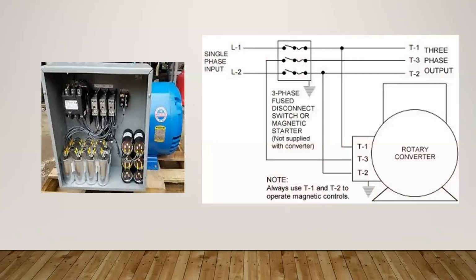The other one that's very heavily in the market is what they call rotary phase converters. And literally what that is, is an induction motor with the shaft cut off. When a motor gets up to speed, it creates a rotary transformer, meaning that it puts counter EMF voltage back to the circuit. So literally what this is, these are the run capacitors in there. These are the start capacitors, and they're bringing this up to speed.